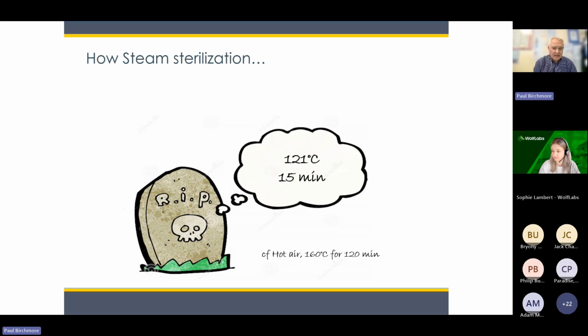In order to kill a cell with heat, its temperature must be raised to a degree at which the proteins in the cell wall break down. Steam is a very efficient medium for heat transfer, which makes it an excellent way to destroy microbes. Air, on the other hand, is a very inefficient way to transfer heat energy. And the difference between steam and air is a thing called vaporization or evaporation.